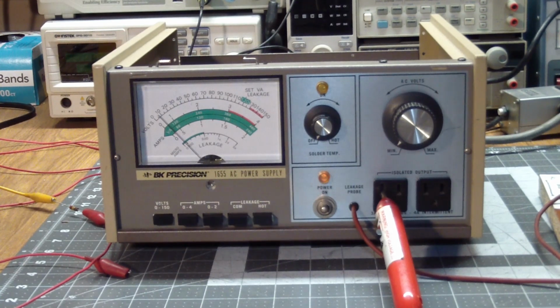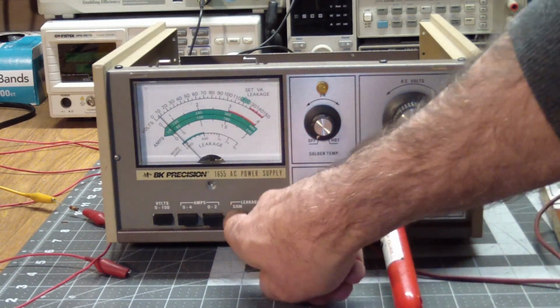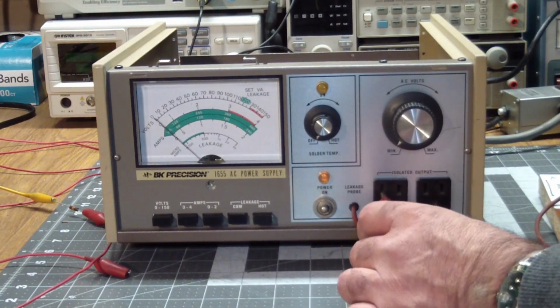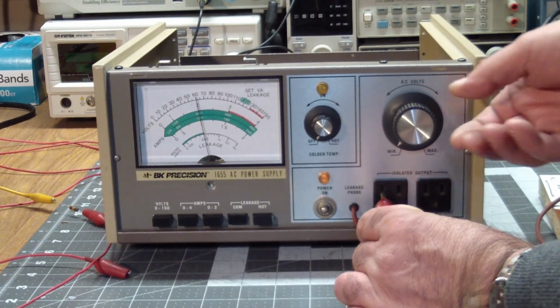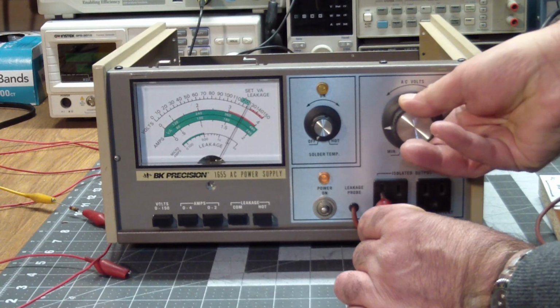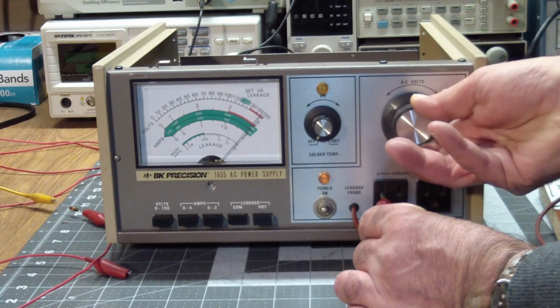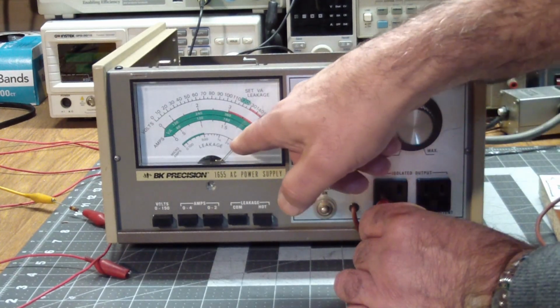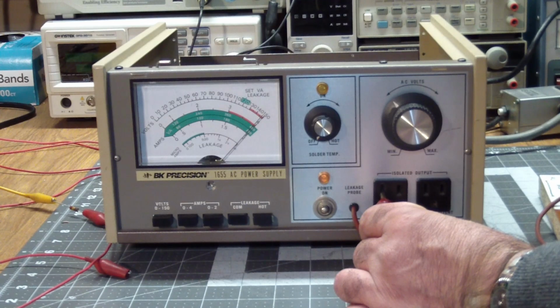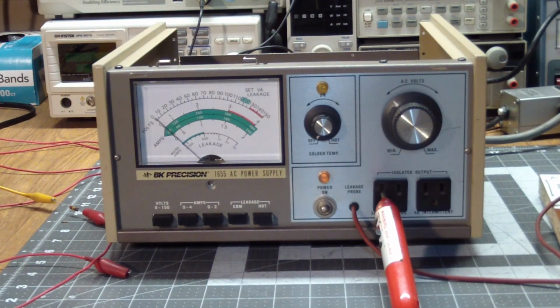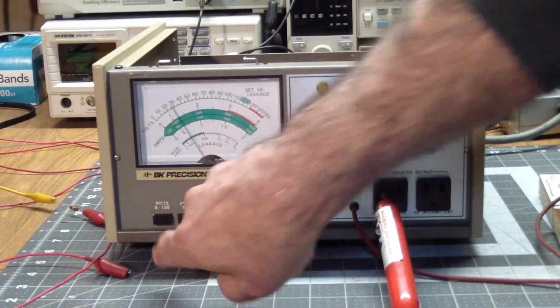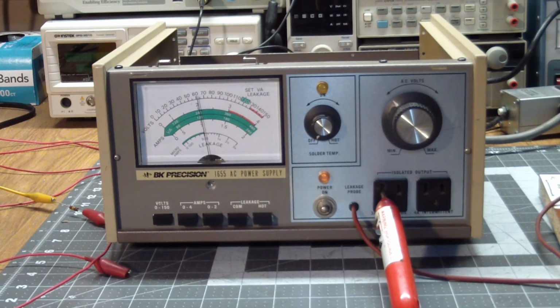And now what we do is increase the AC volts control until the meter reads 5 milliamps on the leakage scale. So we go back here, we press this thing in again, should still be at 500 microamps, and now you increase it till we get to 5 milliamps. It's on the lower scale. It's way out of the green area, of course, but it's showing 5 milliamps now. So how do we know that is correct? Again, it tells us this should occur at about 60 volts. So let's go back to the voltage. Yep, it's at 60 volts. So even though I couldn't go through the calibration procedure, it does seem to work correctly when you're doing the performance test.